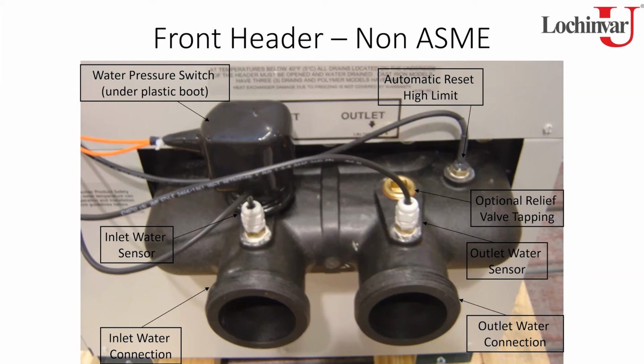So I try not to get too hung up on that delta T unless I see something really, really weird. Again, I prefer to have some sort of flow sensor monitoring what the flow is coming into the unit, so I can't really tell by that delta T what the flow is. It won't tell me, whereas I can see that on other products.